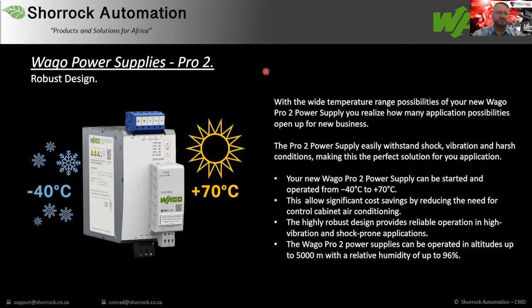The next slide that I'd like to discuss is our robust design. With a wide temperature range possibilities of your new WAGO Pro 2 power supply, you realize how many application possibilities open up for new business. The Pro 2 power supply easily withstands shock, vibration, and harsh industrial conditions, making it the perfect solution for your application. Your new WAGO Pro 2 power supply can be started and operated from -40 degrees Celsius up to 70 degrees Celsius. I'd like to highlight the -40 side of it for some of my customers that have been doing projects up in the Scandinavian countries. This is really important because often they have to actually heat up the panel to compensate for this. The WAGO Pro 2 power supply can actually be started and operated from -40 and will easily run up to temperatures of 70 degrees Celsius.